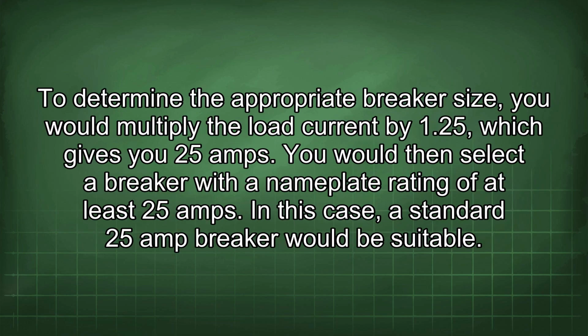To determine the appropriate breaker size, you would multiply the load current by 1.25, which gives you 25 amps. You would then select a breaker with a nameplate rating of at least 25 amps. In this case, a standard 25 amp breaker would be suitable.